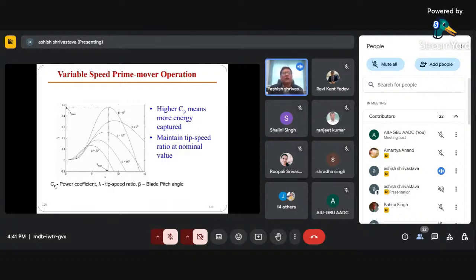This is again for maximum power point tracking. There are two or three important parameters. CP is the power coefficient. Whenever you have to achieve maximum power, CP max, you have to maintain the tip speed ratio at a nominal range. And beta is the blade pitch angle, which is required to be controlled. If wind speed is too high, you change the blade pitch angle, and it can control the wind power or wind flow, so that it will not damage the blade of the wind turbine. Also, the power should not be excessive. So if you have to control the power, you keep on changing the pitch angle of the blade. But if you have to extract the maximum power, then CP max, that is the power coefficient, should be maintained at your nominal tip speed ratio.